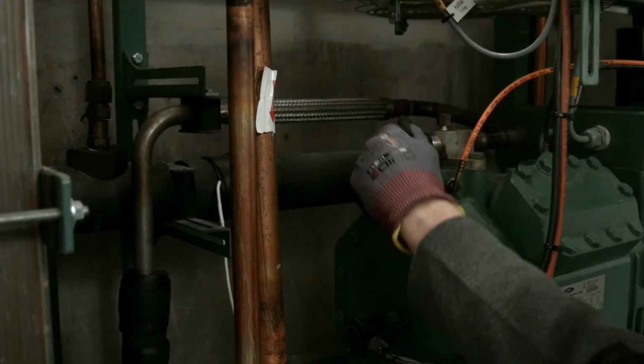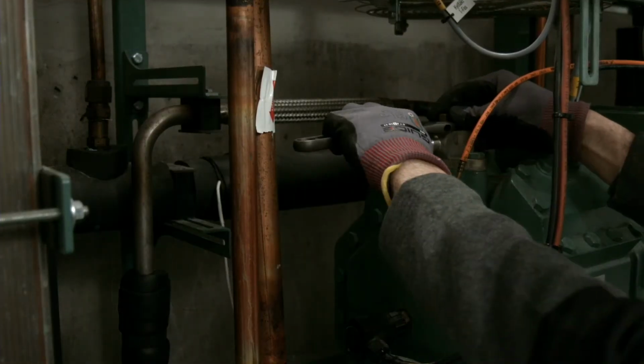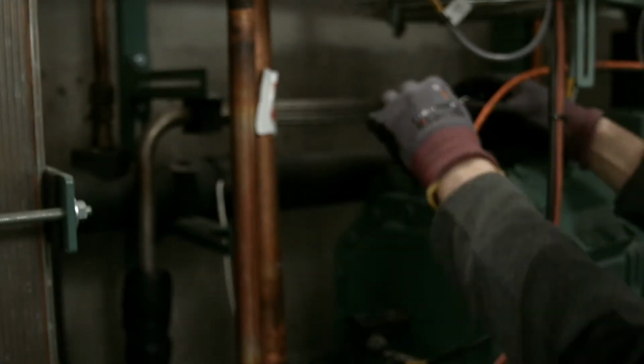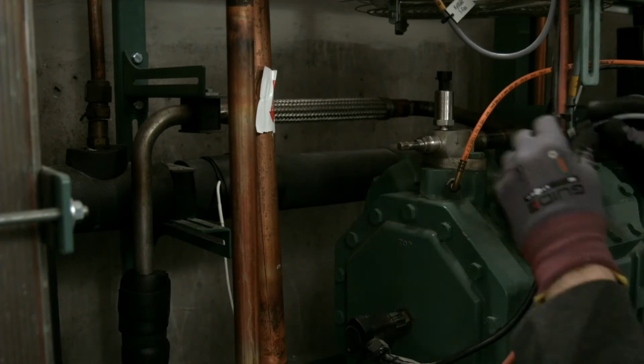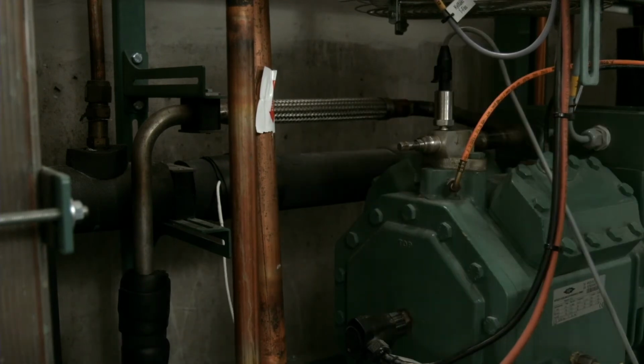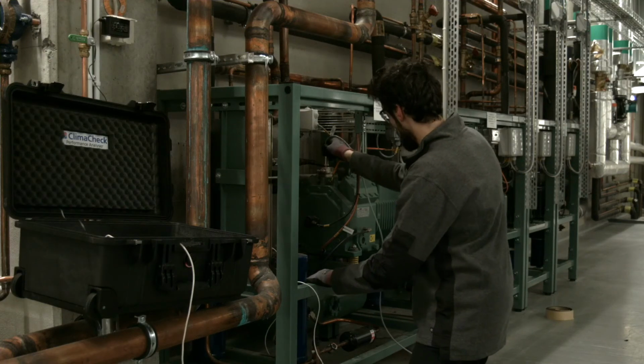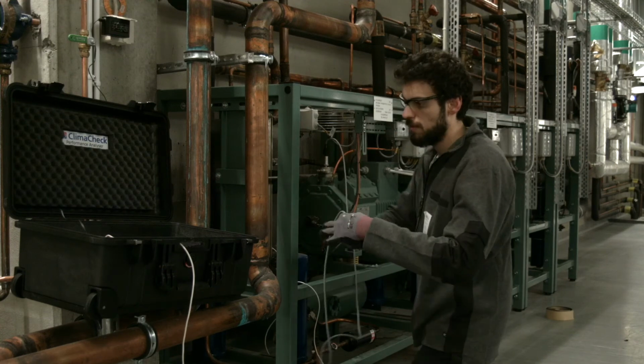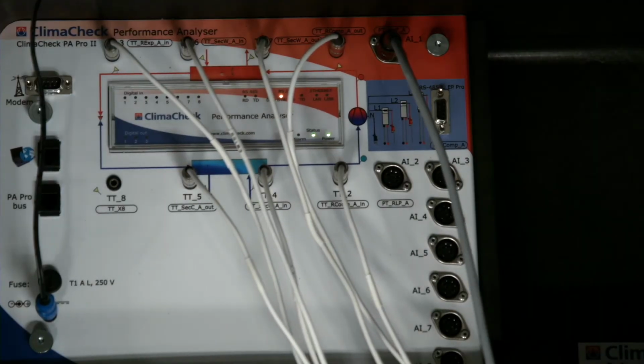Here the pressure transducer is being connected. It has a very, very long throat and a depressor, so they're very, very quick and easy to connect. Special PTFE seal ensures they don't leak. And this is plugged into the discharge pressure transducer port and the suction.